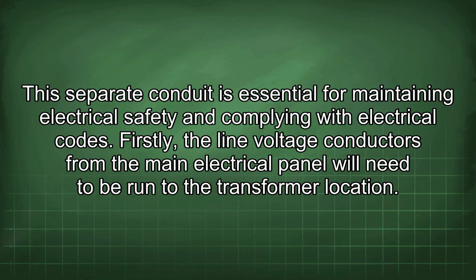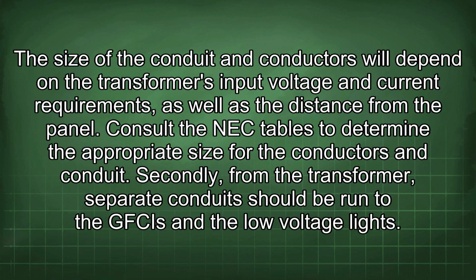Firstly, the line voltage conductors from the main electrical panel will need to be run to the transformer location. The size of the conduit and conductors will depend on the transformer's input voltage and current requirements, as well as the distance from the panel. Consult the NEC tables to determine the appropriate size for the conductors and conduit.